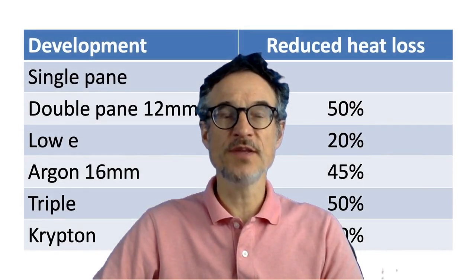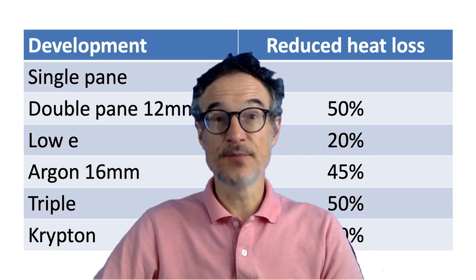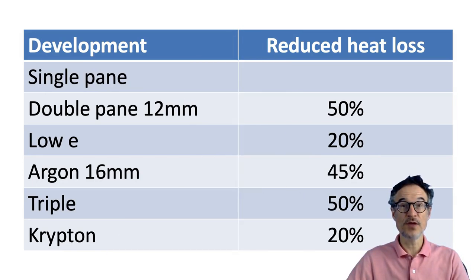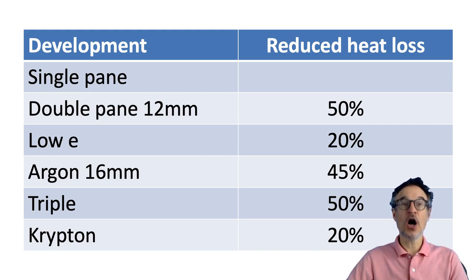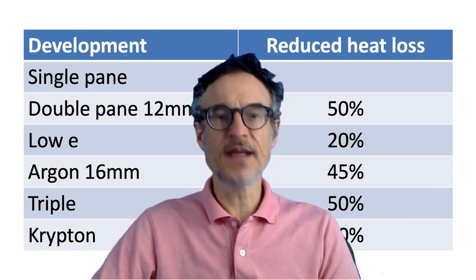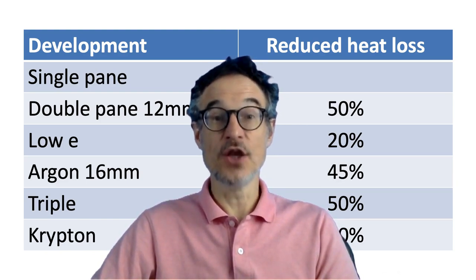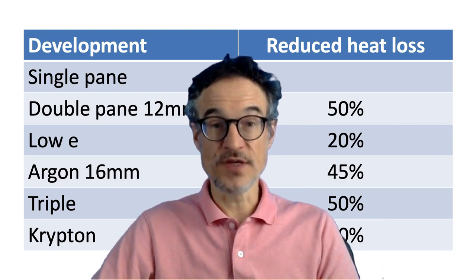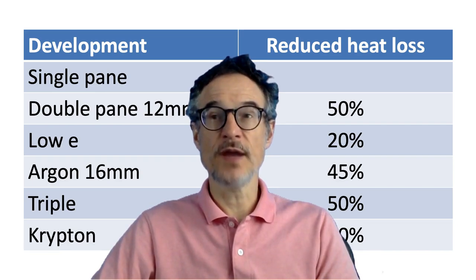Just to remind you from the last session, here are some improvements: double pane windows made windows 50% less heat loss; low-E makes a 20% difference; changing from air to argon and making it thicker makes a 45% difference; going to triple makes another 50% reduction in heat loss; going to krypton gives another 20% reduction. So you can get something like 90% less heat loss by going through all these steps when starting from single-paned glass.